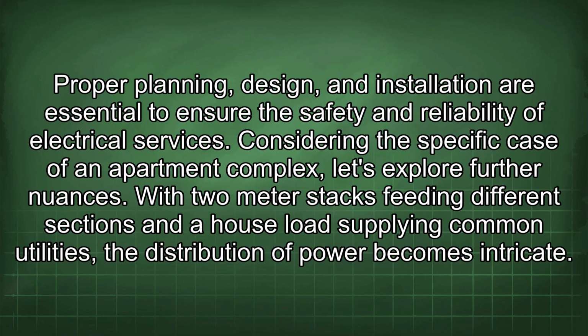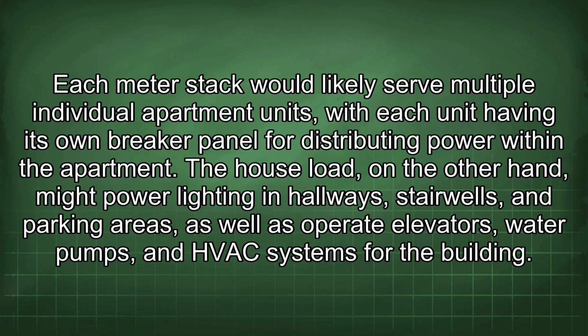Considering the specific case of an apartment complex, let's explore further nuances. With two meter stacks feeding different sections and a house load supplying common utilities, the distribution of power becomes intricate. Each meter stack would likely serve multiple individual apartment units, with each unit having its own breaker panel for distributing power within the apartment. The house load, on the other hand, might power lighting in hallways, stairwells, and parking areas, as well as operate elevators, water pumps, and HVAC systems for the building.